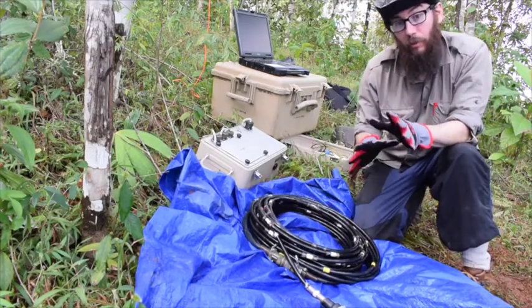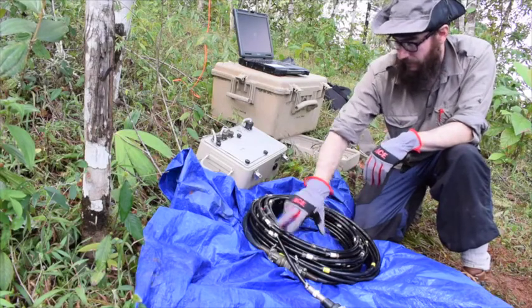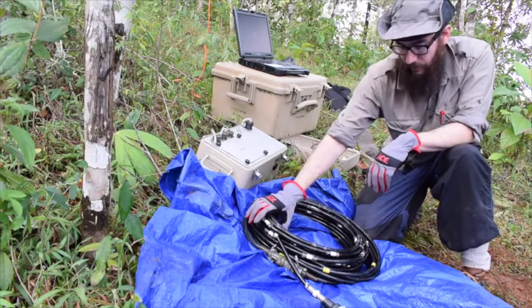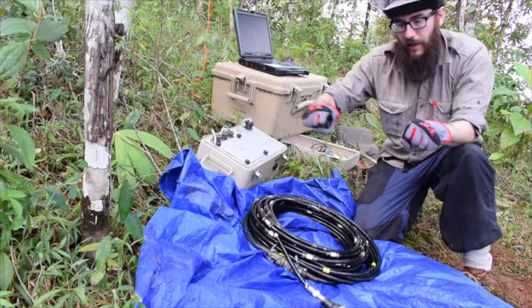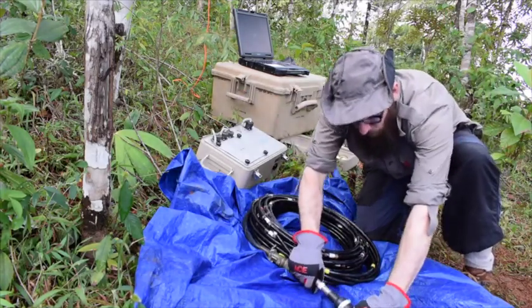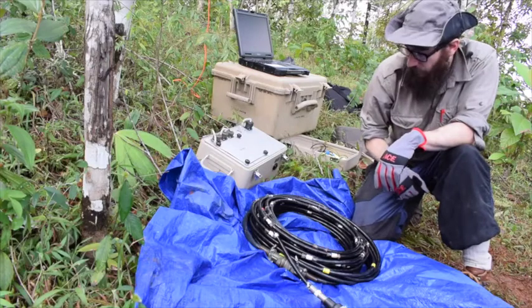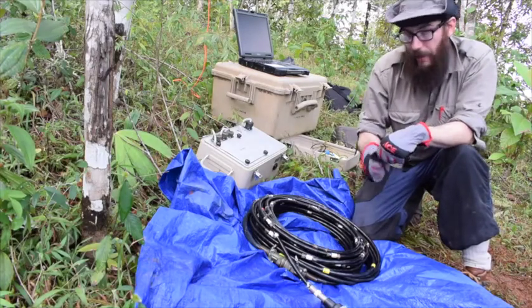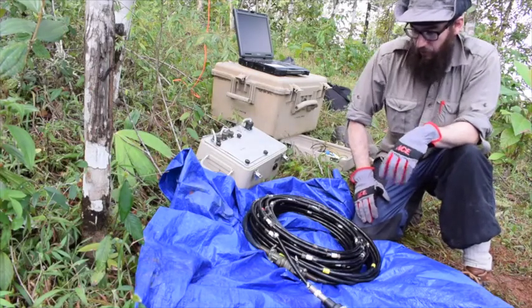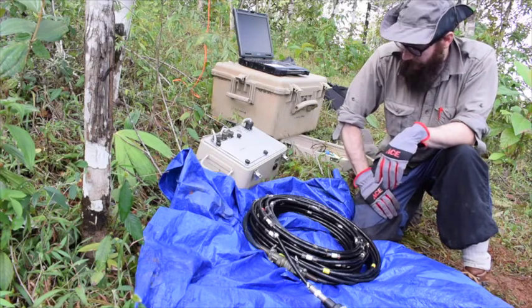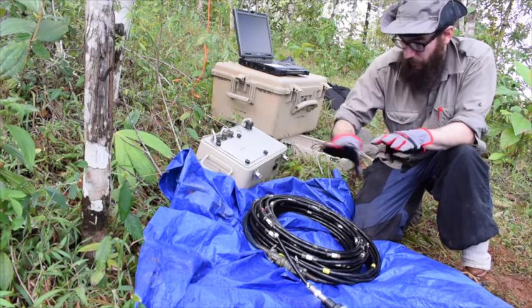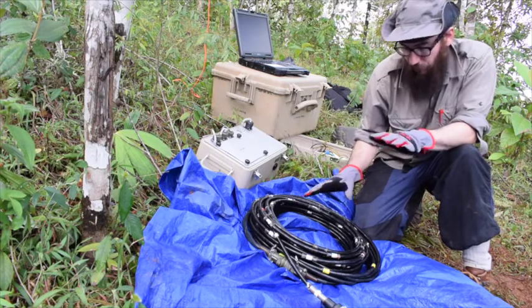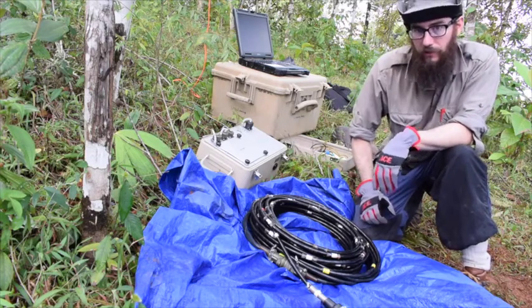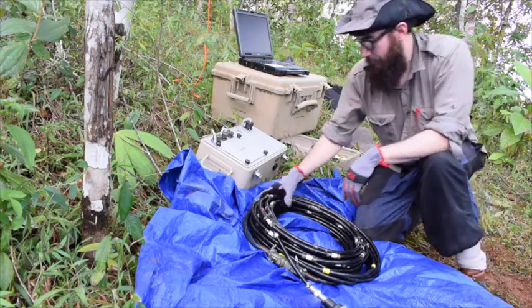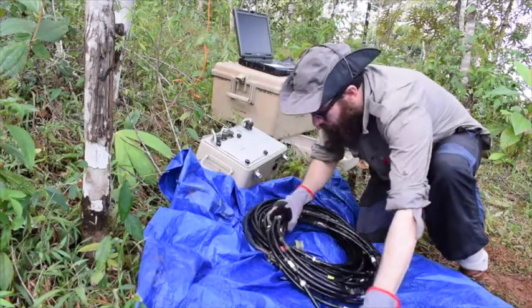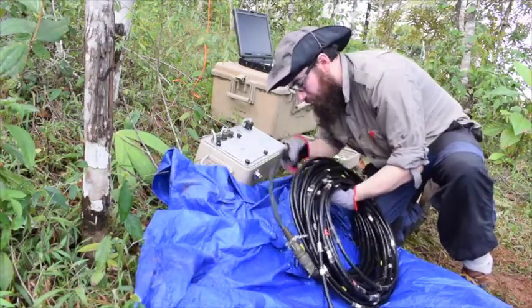unwrapped, it's really important that we respect the cable extremely highly. It's a very strong cable in the direction of gravity when you have it down a well, but it's not very strong in terms of bendiness. So we want to make absolutely sure it doesn't get kinks. And so anytime we're uncoiling it, just be extra careful that nothing gets bent past that 12-inch bend diameter.